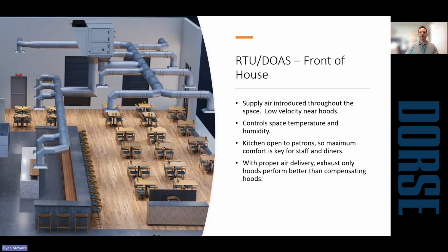So what does it look like? This would be an example where you have an open kitchen, open to the dining room. All the supply air is going to be introduced through ceiling diffusers in the space. You eliminate the compensating hood and you use low velocity, non-directional ceiling diffusers near the hood. It just provides a higher level of comfort for the kitchen staff and the people in the dining area.